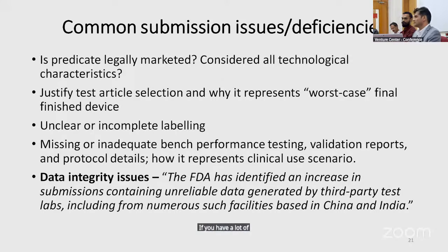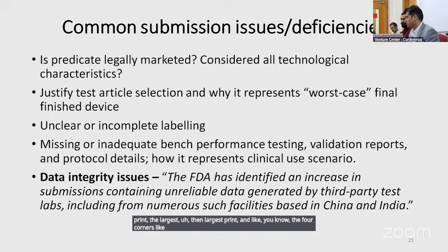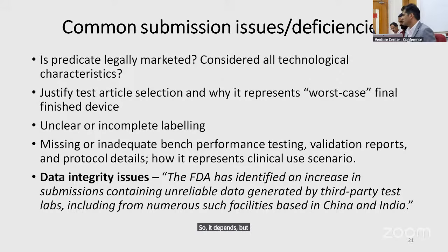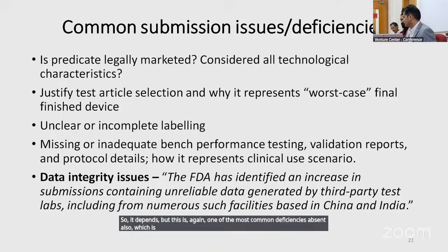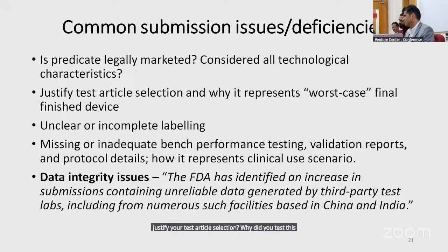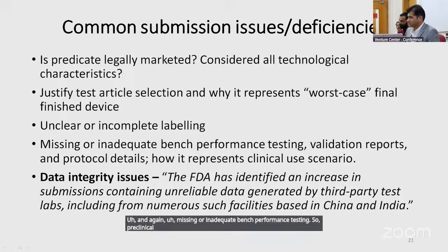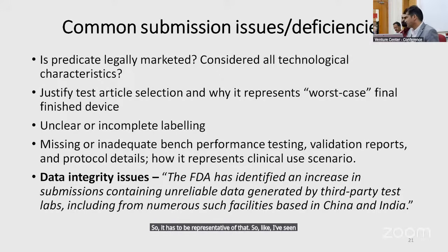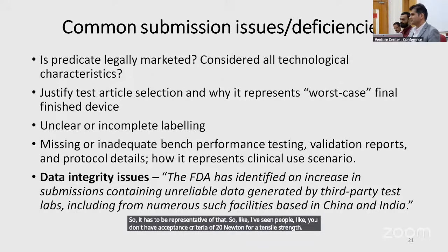If you have a lot of variations, then there's the diamond testing, which is you need one sample from each corner of your specification. So let's say you have length and breadth. Then you're going to need the smallest length, smallest breadth, the largest length, largest breadth, and the 4 corners like that, and maybe a middle one. So it depends. But this is again one of the most common deficiencies I've sent also, which is justify your test article selection. Why did you test this particular configuration of your device, and why does that represent the worst case for your device? The unclear and incomplete labeling, again, very common to have that. And again, missing or inadequate bench performance testing. So all preclinical testing is supposed to be representative of the clinical and the anatomical use. So it has to be representative of that. Like I've seen people have acceptance criteria of 20 Newton for tensile strength. Where that comes from, no one knows.